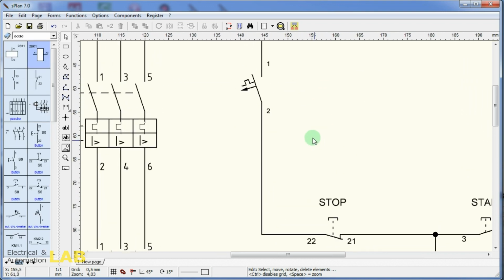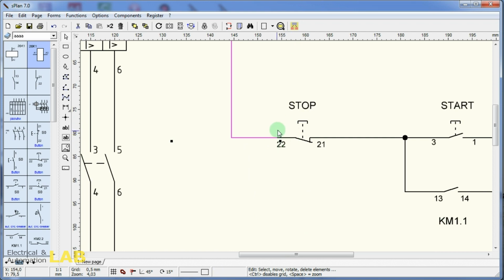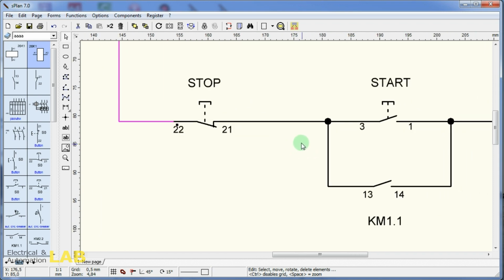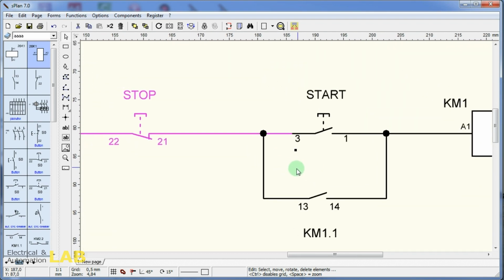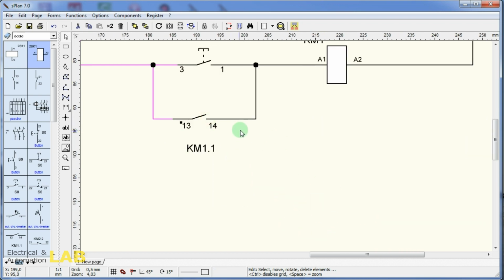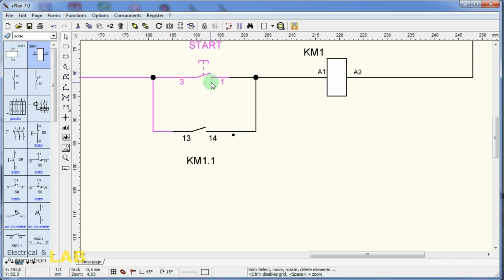Let's see in what sequence our scheme works. After turning on the automatic protection of control circuits, a phase appears in front of the stop button. Stop is always closed and therefore power goes through it immediately to the start button. At the same time, the power is divided into a start button and an additional contact of the KM1 contactor. Press the start button, power is supplied to the contactor coil, KM1 is turned on and the additional contact of KM1 is also closed. The contactor switches to self-supply.